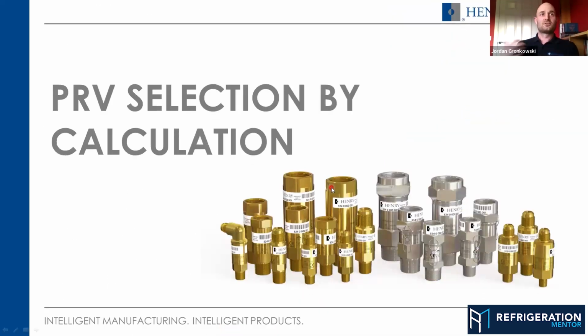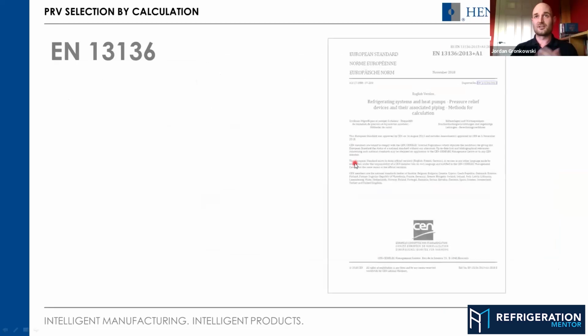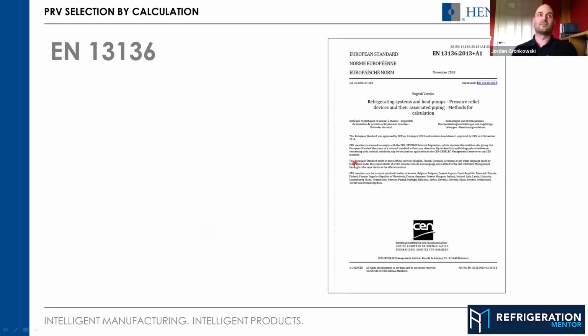So, jumping into the selection by calculation method. As we've touched on, I'm sure you all know, the most important thing with the PRV is that it is your last line of defense. It needs to be sized correctly. If it's too small, it won't protect the system. If it's too large, as we discussed earlier, you get chattering and issues.